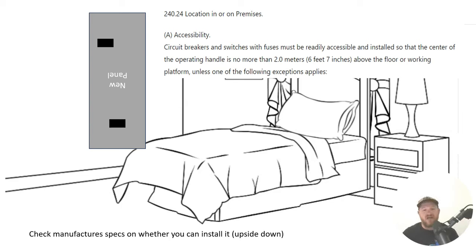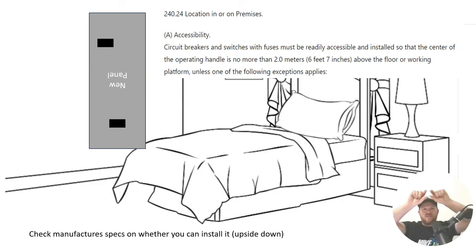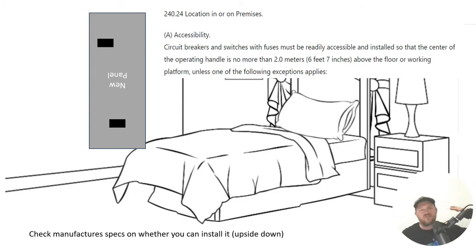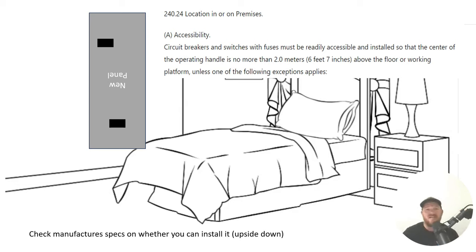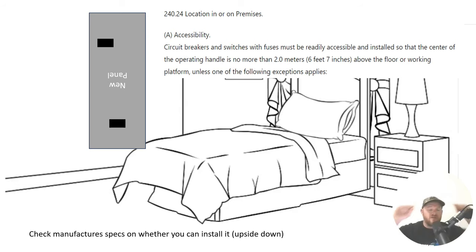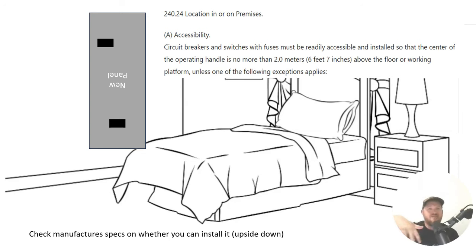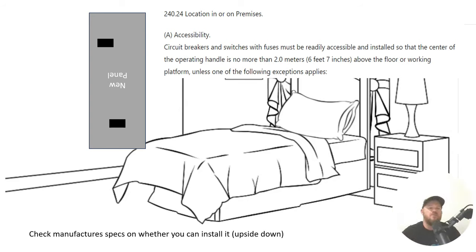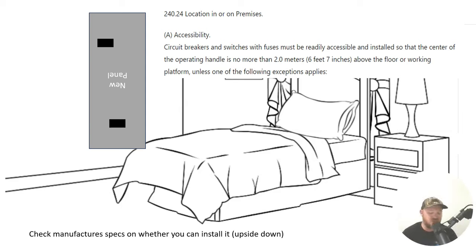And in my opinion, like in this scenario today, if you flip that panel upside down and let's say you're not even using those unused spaces and you use all of these lower spaces closer to the main breaker. And you're like, oh, none of the breakers I've installed today are over 6 foot 7. If I'm your inspector, I'm going to say that includes also any of the available breaker spaces because we know in the future when someone pulls a circuit in from the top, they're likely going to use one of the ones closer to the top because it's easier. It's safer to wire. There's not a bunch of wires in their way. So just keep that in mind when you're out in the field. Now that will be subject to your AHJ and how they handle things.